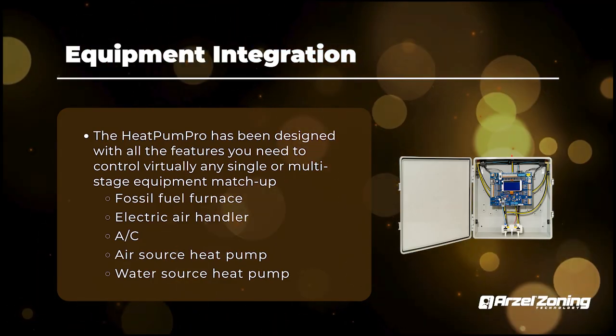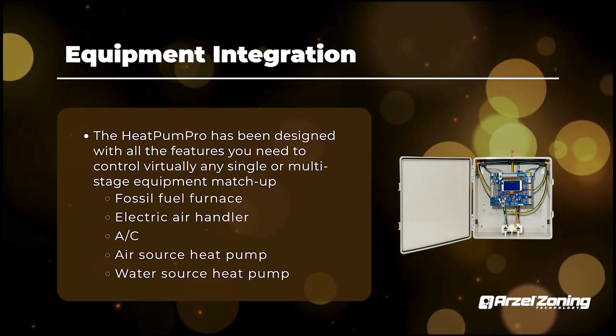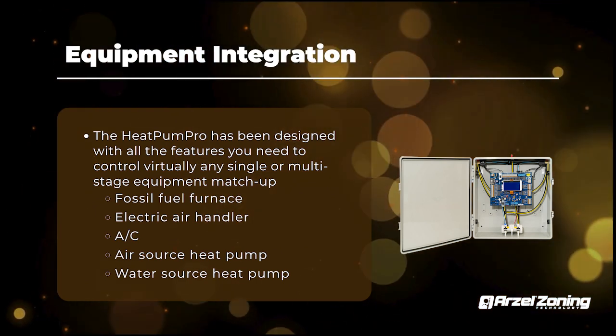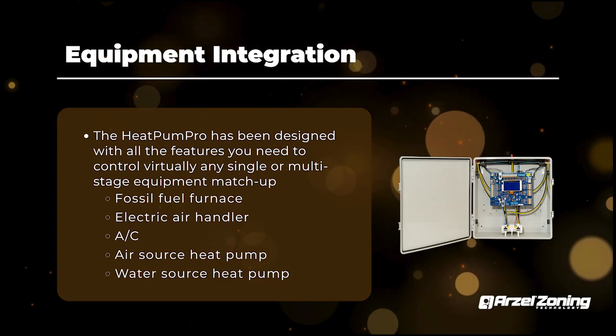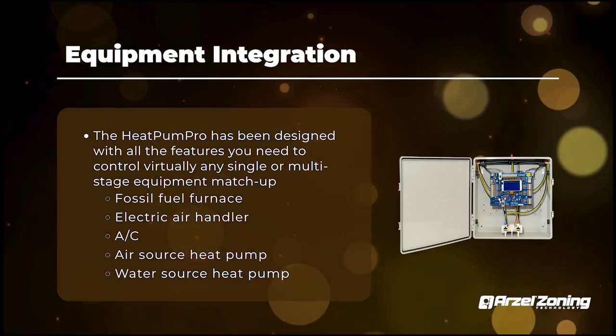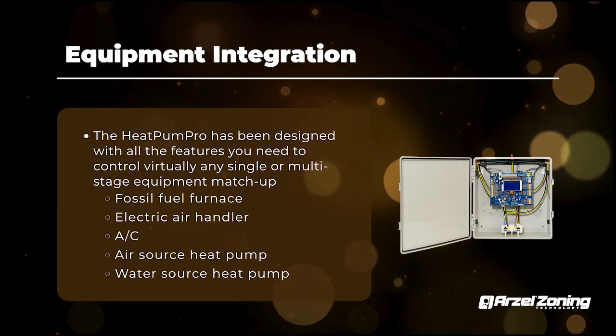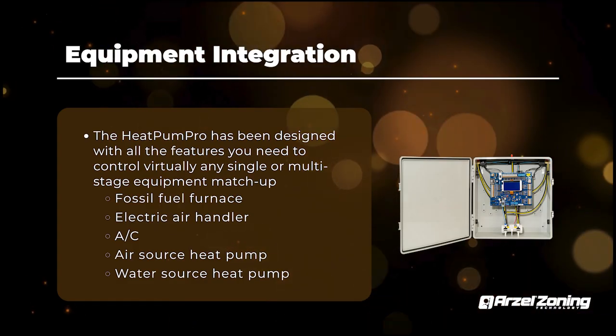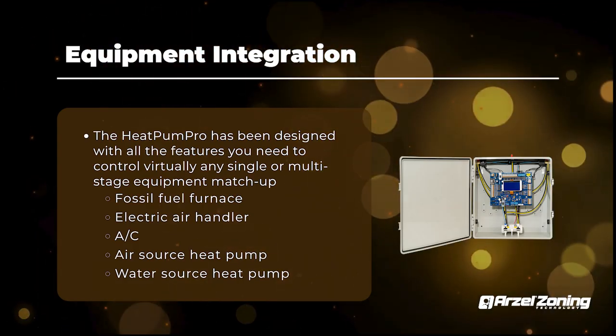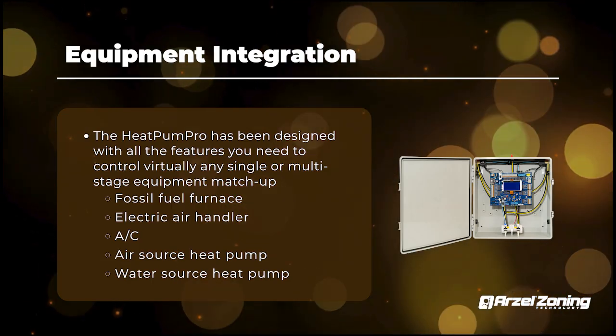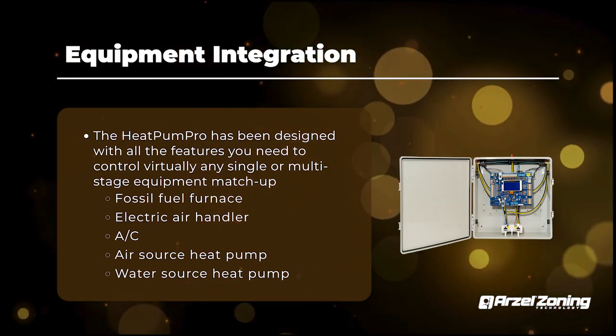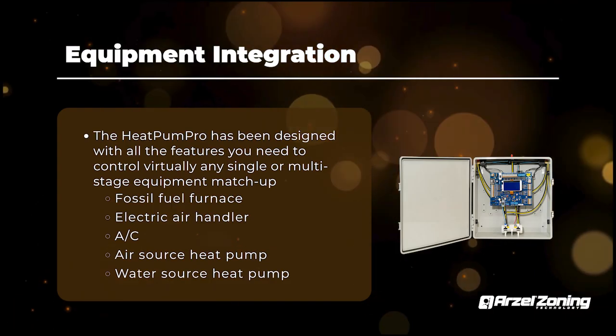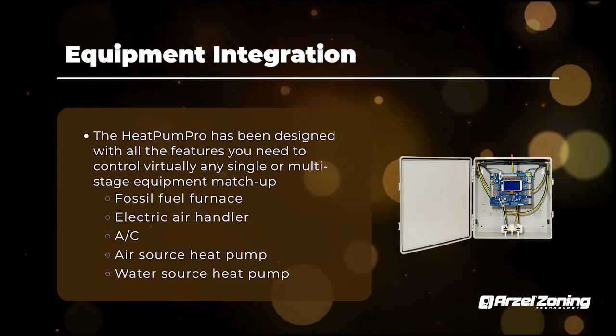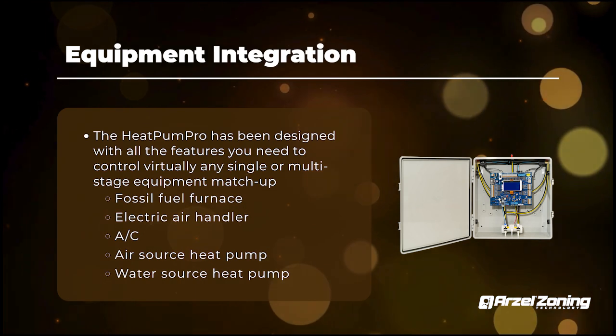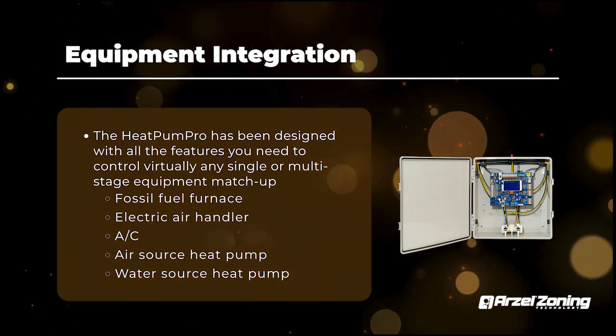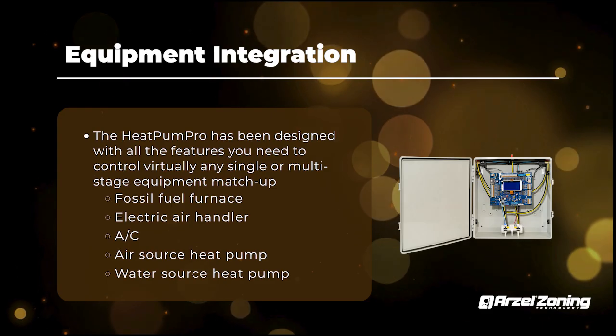The panel itself is going to ship with a leaving air temperature sensor, which will give you your high and low temperature limits. It's also going to ship with an outdoor temperature sensor as well. That's going to go outside. If you have a heat pump application or a dual fuel application, you're going to run that sensor outside, and that's going to provide you with your changeover temperatures, but it'll also give you resistance heat lockouts and that kind of stuff as well. We'll touch on that a little bit further along. So really, you don't need any additional controls. The panel will do up to 35 dampers as shipped. It'll control up to 35 dampers on one system.